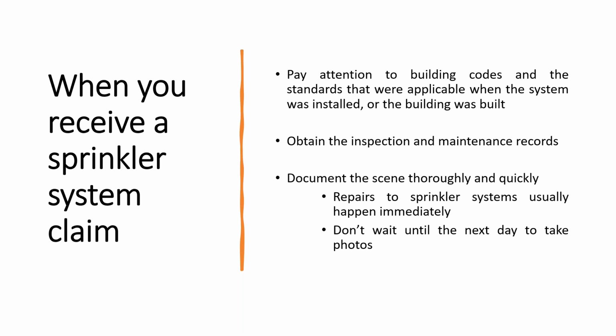A few other quick tips on subrogation and legal files when it comes to sprinkler system claims. Again, the standards include details relating to the installation, to the inspection and maintenance of the systems. But think outside the box, right? A failure in one point of the system may have its root cause somewhere else. So don't only focus on the area where it failed. For example, a freezing failure is not necessarily that it was freezing outside, but something was wrong in the installation or maintenance. So yes, it froze. Yes, it was cold, but was someone supposed to take care of draining the system beforehand?